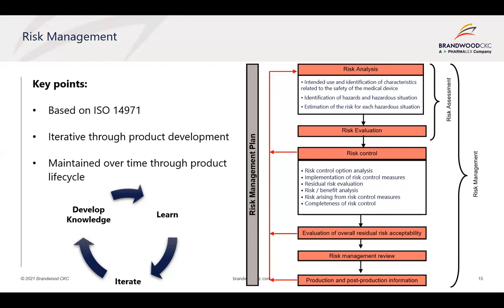So there are a number of documents that are expected as part of that, the deliverables for compliance to that standard. That includes a risk management plan where you'll be identifying your criteria for risk management, the team that's going to be involved in the risk management process, in the approvals, the analysis, and all of those phases, and the methods that you're going to use to evaluate the risks. And then subsequently to this plan being established, follow phases of actual evaluation of the risks and the final reporting. So one point that's quite important to highlight here is that it's quite often missed that preliminary risk analysis should be documented quite early on, as soon as you're aware of the device intended use, so that those inputs can actually flow into your design process and you'll be able to identify product features, and types of testing that you might need to conduct and that require verification and validation, early on.